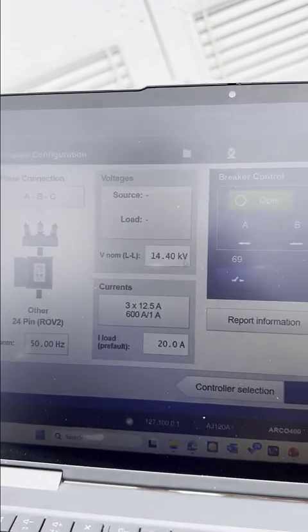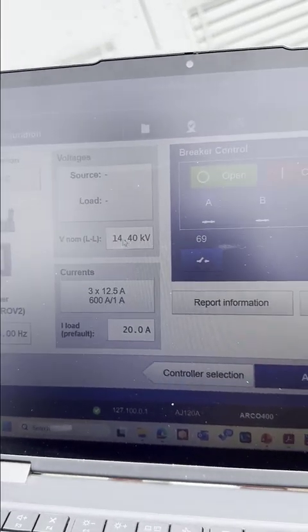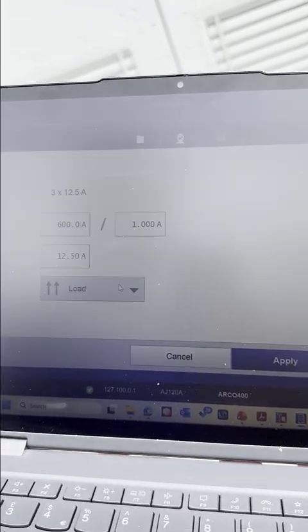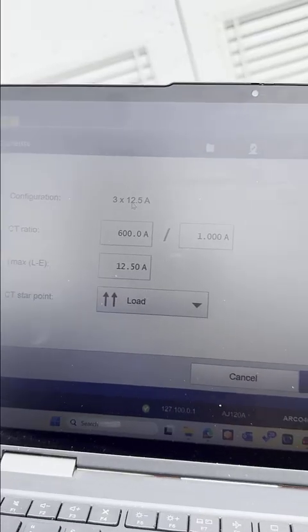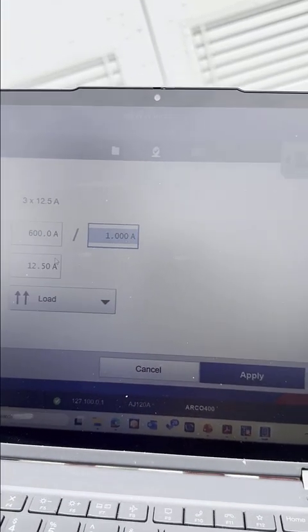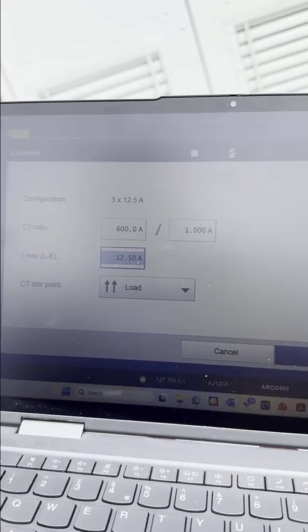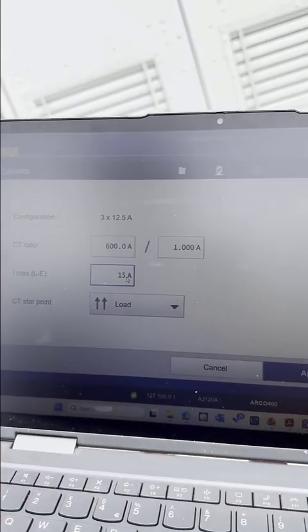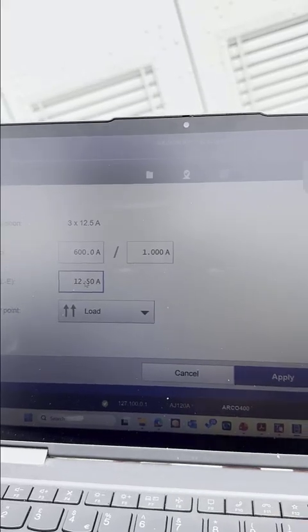Here is the nominal voltage. Also, in case you have a VT, you can specify this nominal voltage in line to line. And then we have the current. We have 3 phases of current up to 12.5 ampere per channel, and the CT ratio is 600/1, and the maximum for sure is 12.5 ampere. And if you put in more than this value by mistake, it will go back again to 12.5, because this is the maximum amplitude of the current channels.